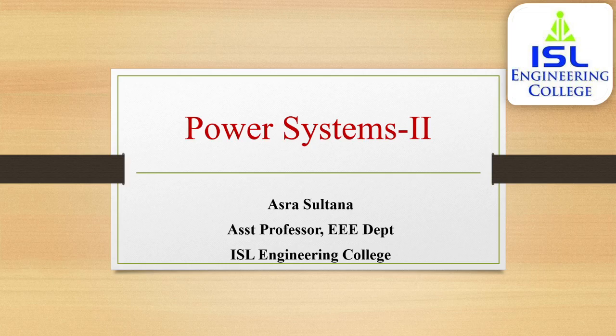Conversion can be effected by using the following relation. Percentage reactance at base kVA is equal to base kVA by rated kVA into percentage reactance at rated kVA. So a 1000 kVA transformer with 5% reactance will have a reactance of 10% at 2000 kVA base. With the help of a numerical also we have seen it. If you choose any base kVA, for example, in a problem we have seen once for 2500 kVA as common base, and once for 5000 kVA, in both the cases the short circuit current will be the same.